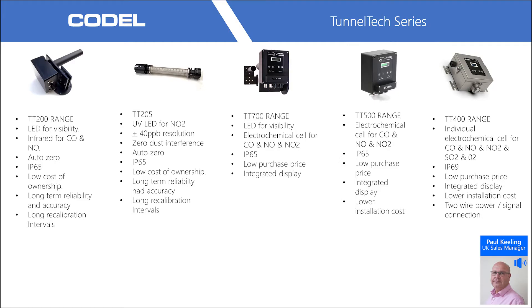So the gas analysing range. Firstly, the TunnelTech 200 range — each one is subdivided into a range of analysers with different combinations. You have visibility there measured by a high-power LED, and we use infrared on this range to measure CO and NO in any combination. All of these devices are minimum IP65, with very low cost of ownership and easy installation. We look for long-term reliability and stability with long times between recalibration. The TunnelTech 200 is the main backbone of the infrared range. Of course, you cannot measure NO2 with visible or infrared.